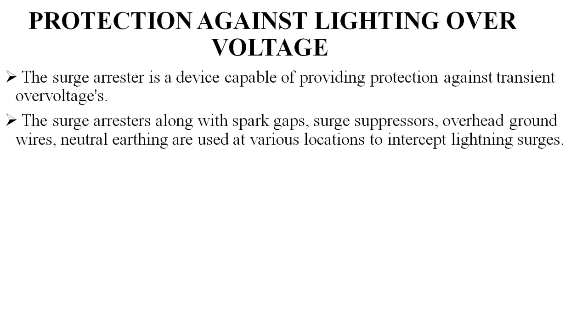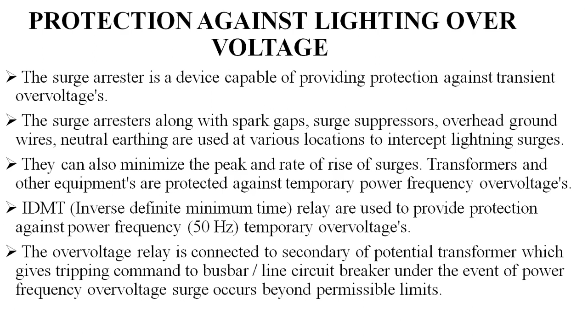The transformers and other equipment are protected against temporary power frequency overvoltages. IDMT relay, the inverse definite minimum time relay, is used to provide protection against these power frequency temporary overvoltages. The overvoltage relay is connected to the secondary of the PT, which gives a tripping command to the bus bar or line circuit breaker in the event a power frequency overvoltage surge occurs beyond the permissible limits. The following table shows the type of overvoltage and corresponding protective devices. See, this is the type of overvoltage, protective devices used, and operating time.